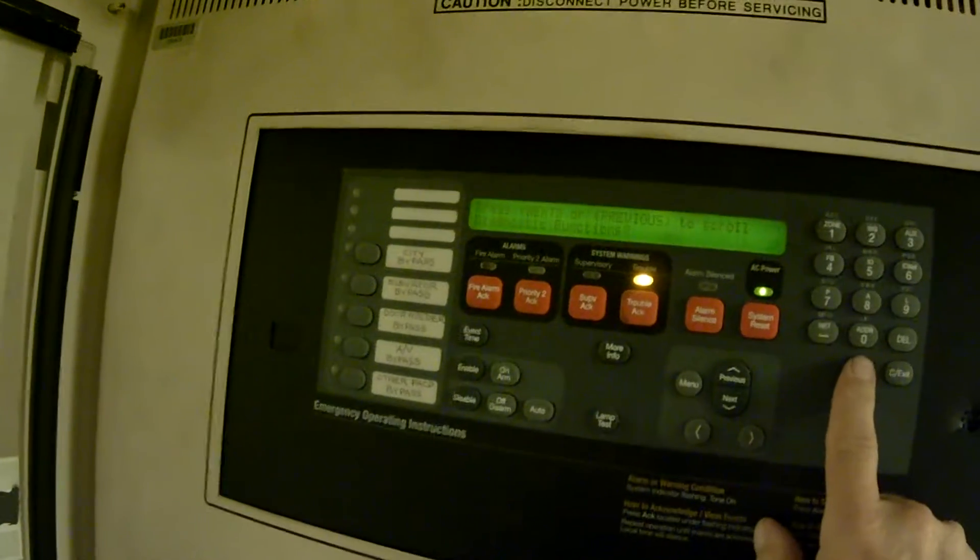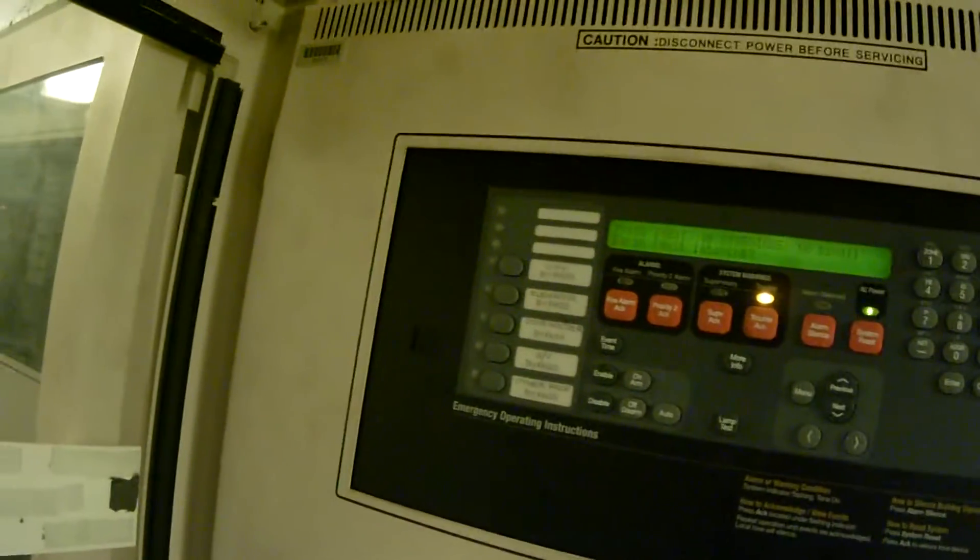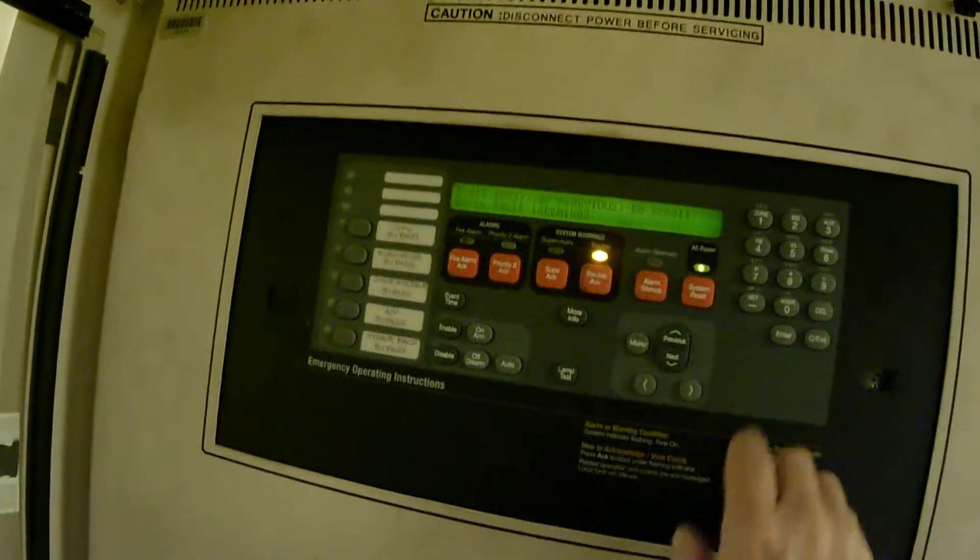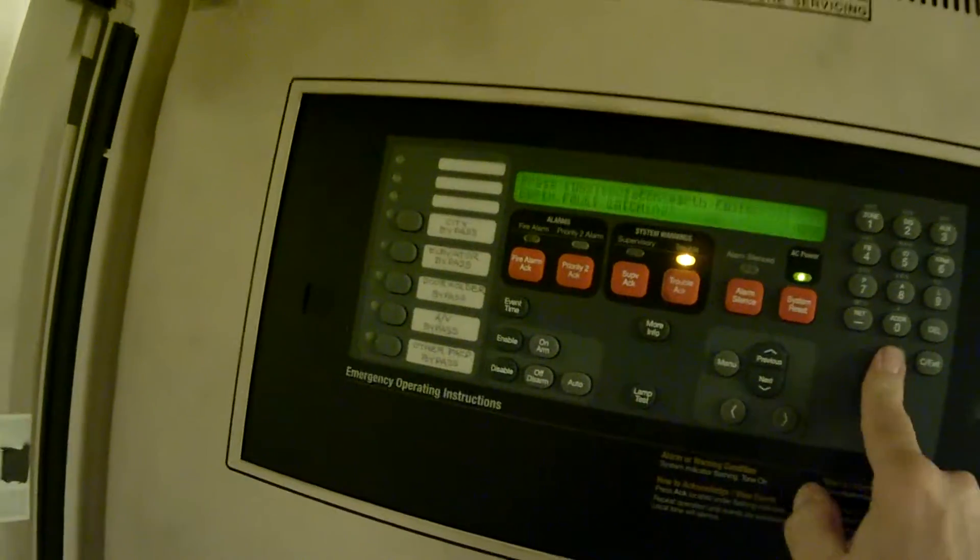Diagnostic function—that's what I want. Press enter. My first selection on this panel here is earth fault latching. If it doesn't say earth fault latching, we have to press next or previous until we find earth fault latching within the menu. Once we get to earth fault latching, we press enter.